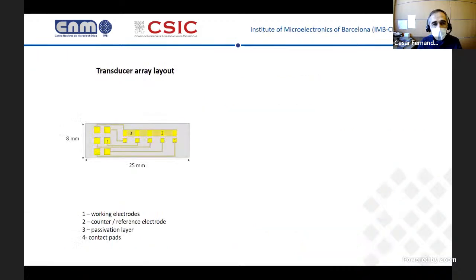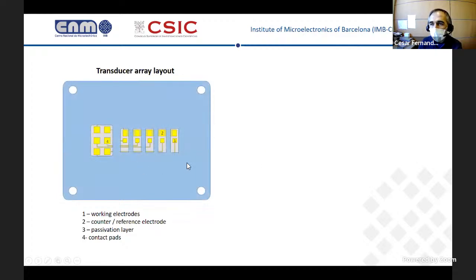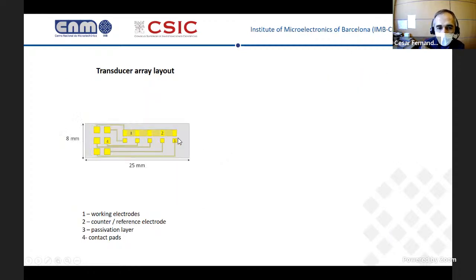in flow conditions. So the array consists of 5 two-electrode electrochemical cells that share a counter-reference electrode. One of the particular features of this transducer array is that the counter-reference electrode has just one contact pad, but still can be compartmentalized to get the 5 electrochemical cells in the array. There you can see the different components of this array: the 5 working electrodes of each electrochemical cell, the counter-reference electrode that has been divided into these 5 areas by using a silicon oxide passivation layer, and also the 6 contact pads, 5 for the working electrodes and 1 for the shared counter-reference electrode.